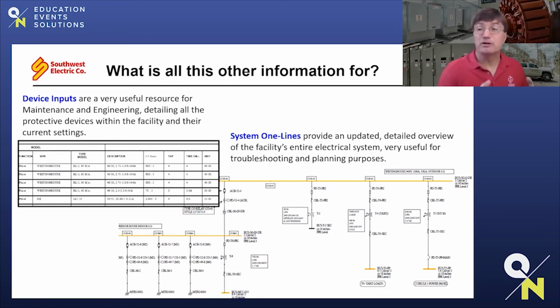So besides this critical information regarding the arc flash incident energy levels and possibly how to mitigate them, we also have other information included in this assessment. So you have all the protective settings throughout the electrical system, your fuse ratings, fuse curves, your relay settings, your breaker settings, all these are listed under the device inputs. This is very handy information for your maintenance or your engineering departments to have if they ever wanted to do any kind of modification or upgrade in your facility, if they ever wanted to relook at the protection, or if they're trying to troubleshoot an issue.